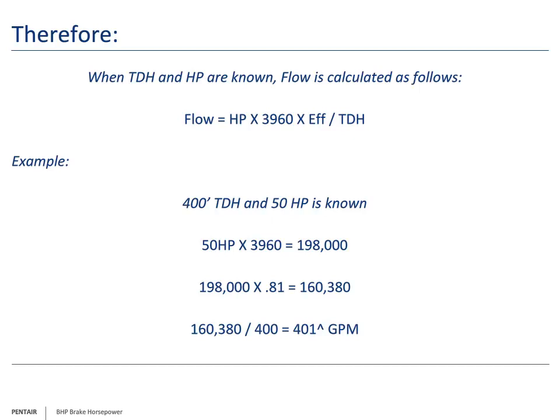Finally, what if gallons per minute are in question? Often a system is designed and then a limitation pops its head up. It is common that the power authority can limit the horsepower of the equipment to be used. By manipulating the formula we can solve for gallons per minute. An example: a booster system as designed is needing 400 feet of head but is limited to 50 horsepower. Doing the calculations, the first result indicates that it should be achievable.